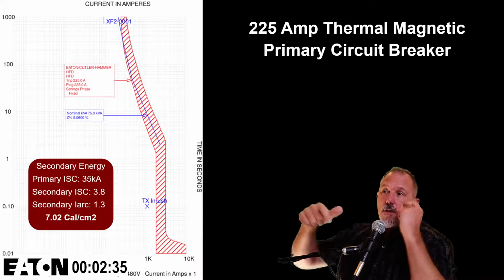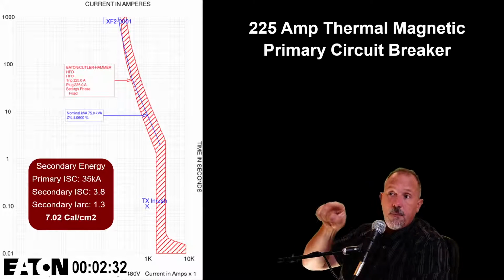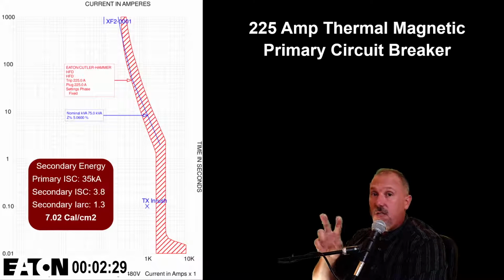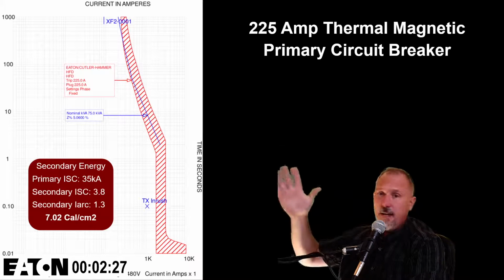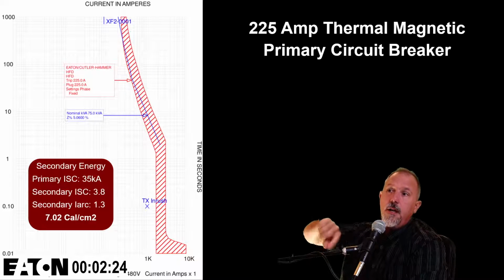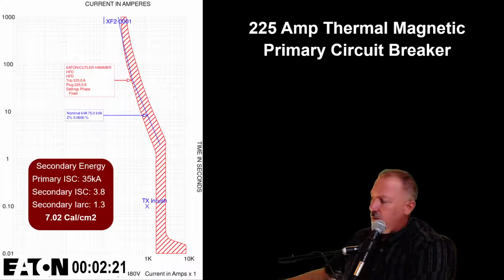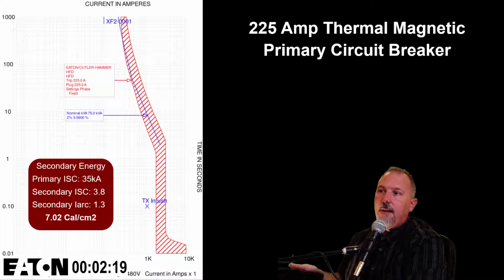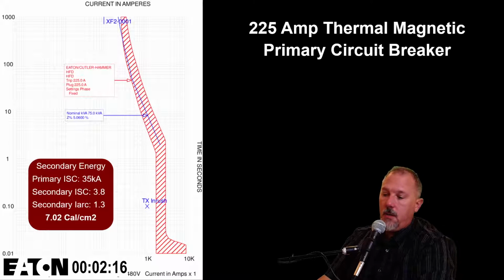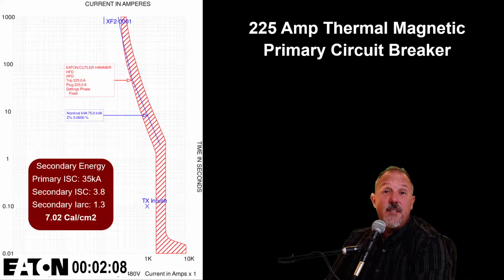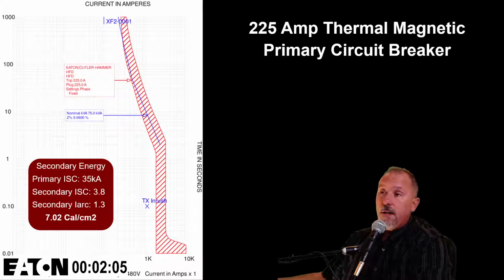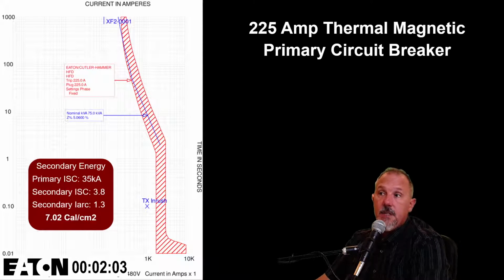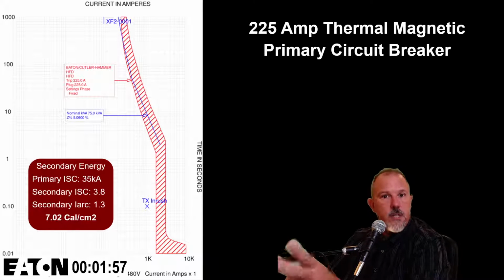So that primary overcurrent device, in this case, 7.02 calories is based upon a 2-second clearing time because that primary, the fault current, the arcing current, that secondary arcing current, 1.3, so that's 1,300 amps. When I say 1.3, that's 1.3 kiloamps. So 1,300 amps times 208 divided by 480 is 563 amps. The primary device during an arcing fault is only going to see 563 amps.